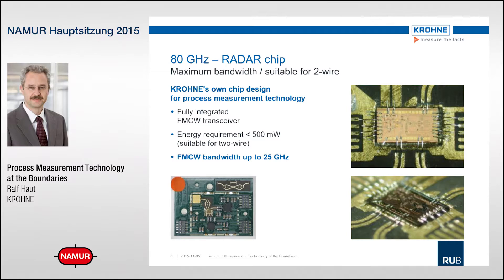This chip is suitable for two-wire measurement because the energy requirement is less than 500 mW. It includes a fully integrated FMCW — frequency modulated continuous wave — transceiver and performs a bandwidth of up to 25 GHz. It is not taken from other industries like the automotive industry; it is particularly developed for the process industry.